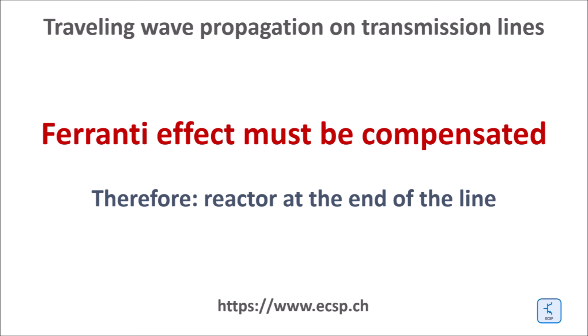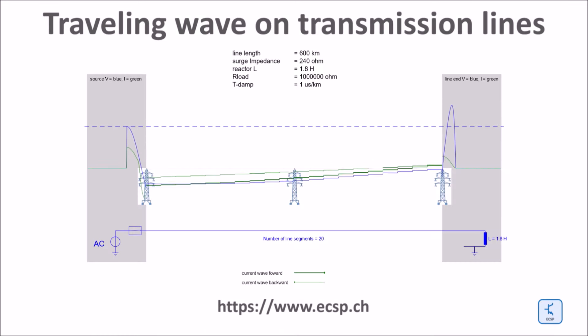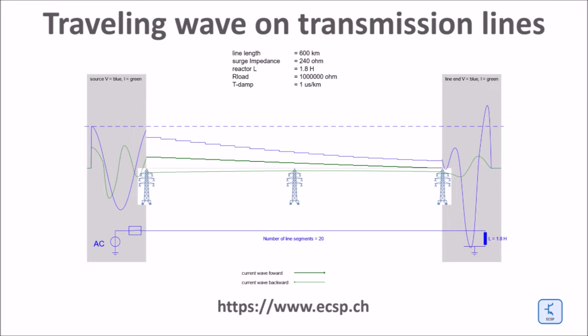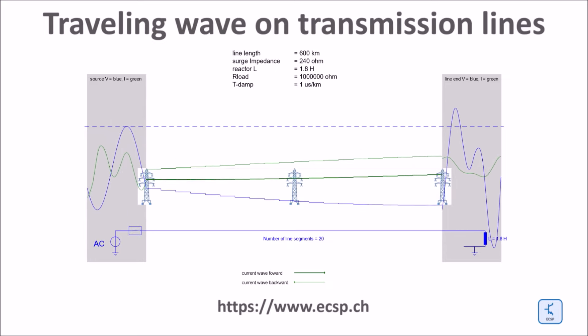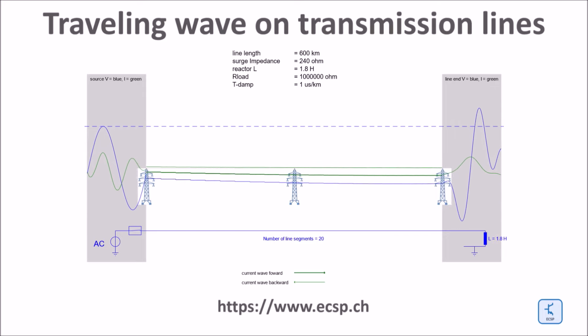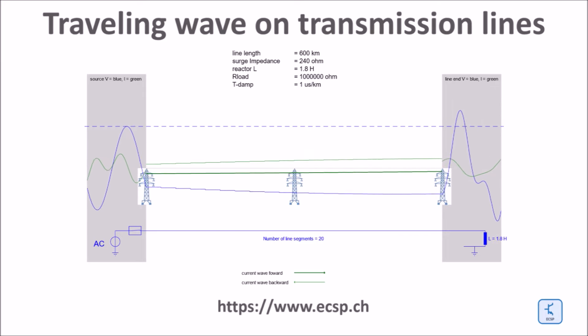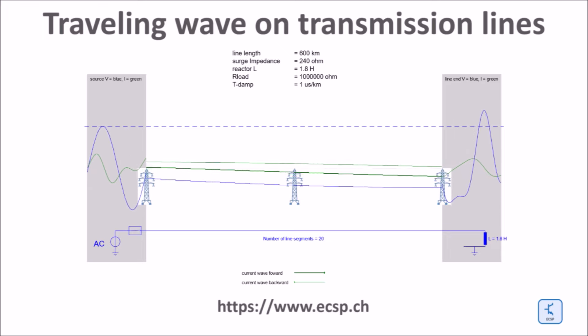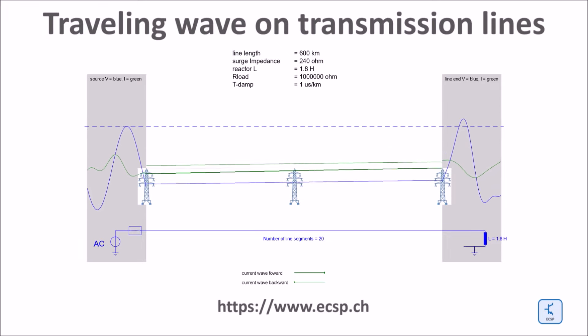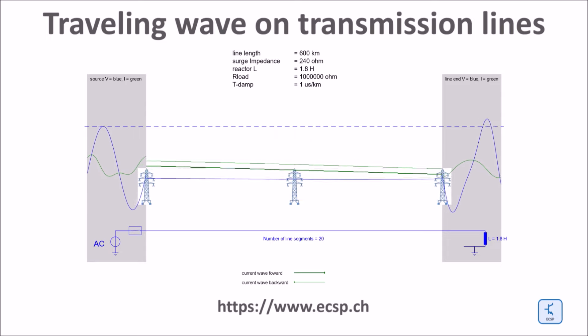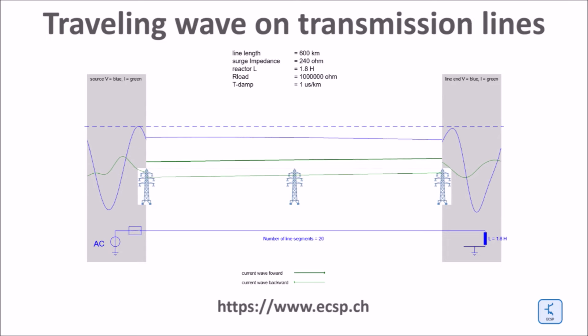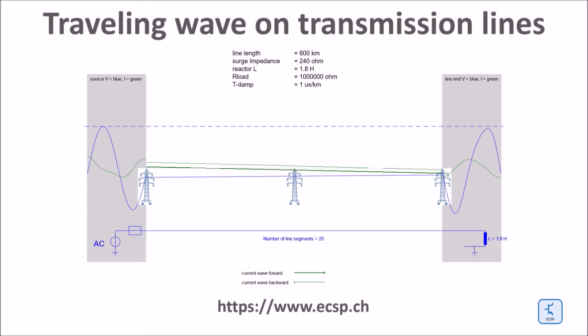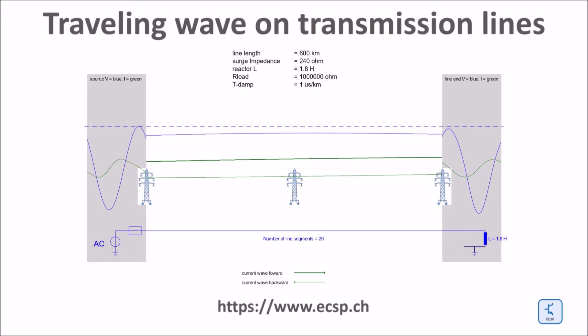A reactor at line end, properly adjusted to the reactive power consumption of the line, can fully eliminate the overvoltage at the end of the line. An open line exhibits a capacitive characteristics. Therefore a reactor is needed for overvoltage reduction. In this example I put the reactor at the end of the line only. In reality however, the reactor would be distributed to both ends of the line, and in case of very long lines, an additional compensation might be needed in the middle of the line.